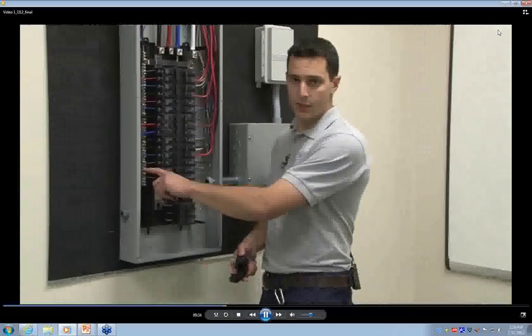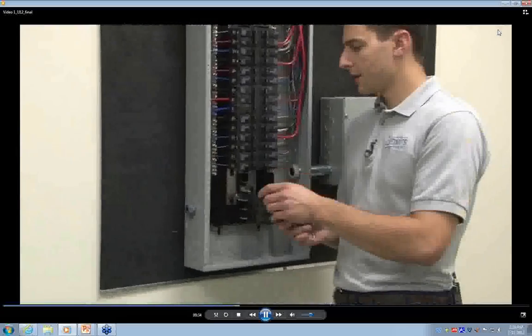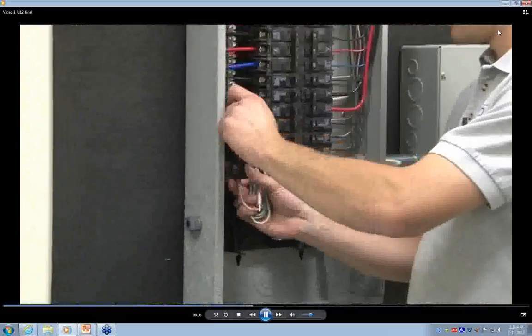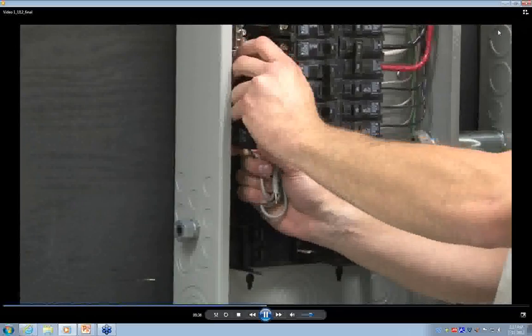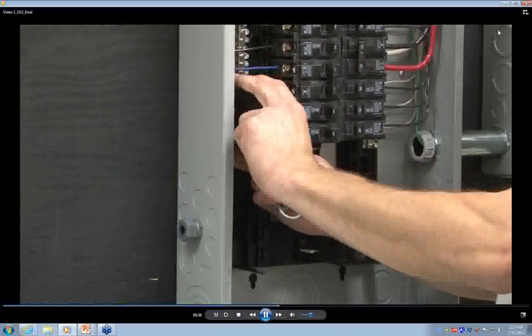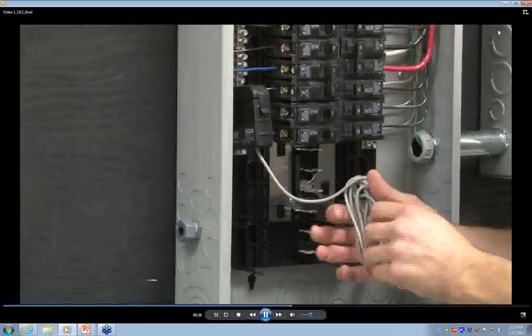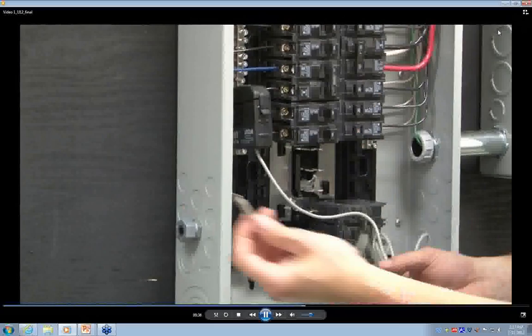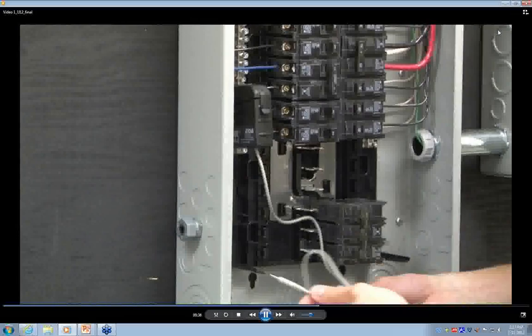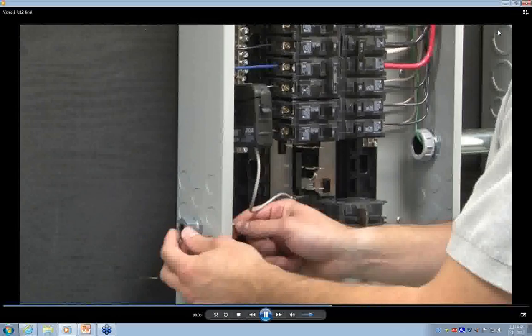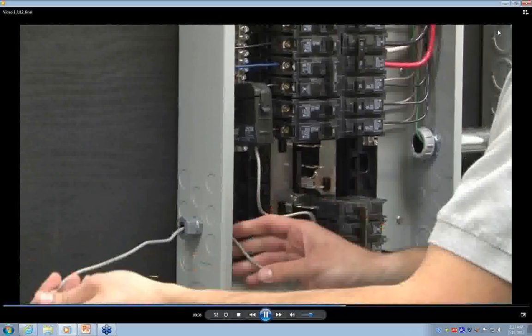Once we've identified the circuit to monitor, we'll install the CT around the conductor, line up the conductor in the center of the CT, and clip it closed. And now we'll need to run the data cable to the outside of the enclosure. We'll do so by running it through this fitting. That way it'll provide a safe method of exiting the enclosure.